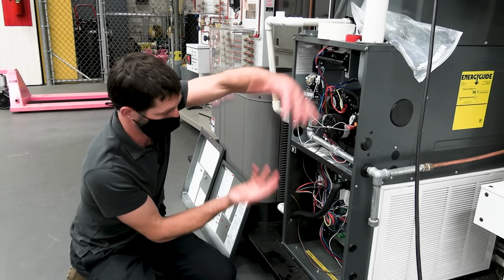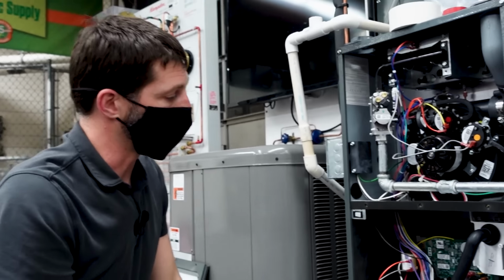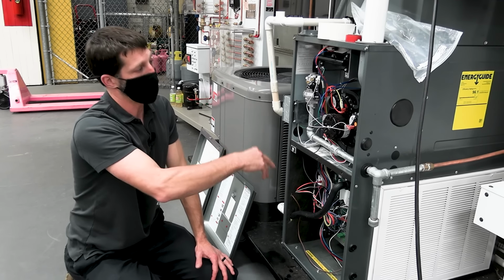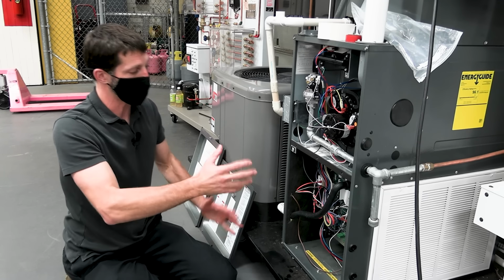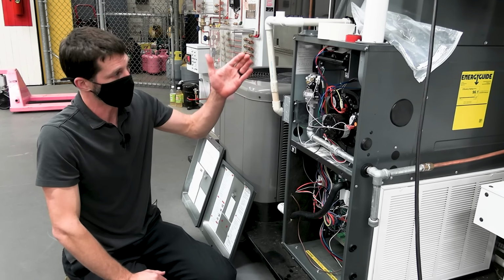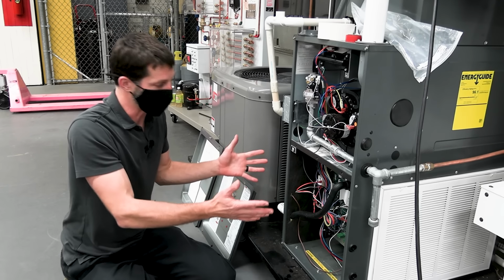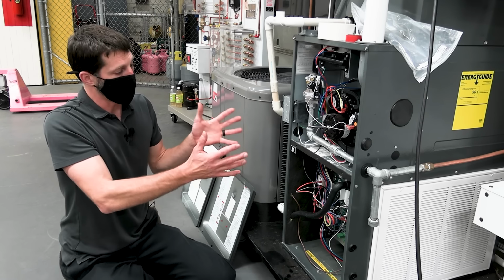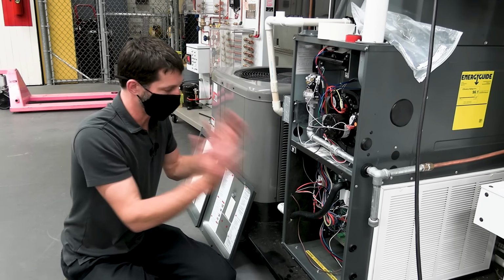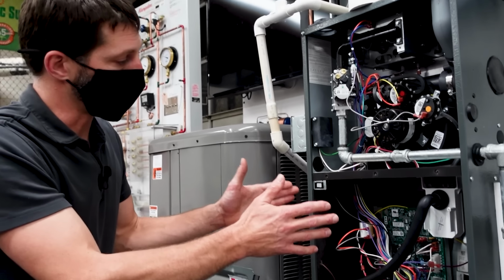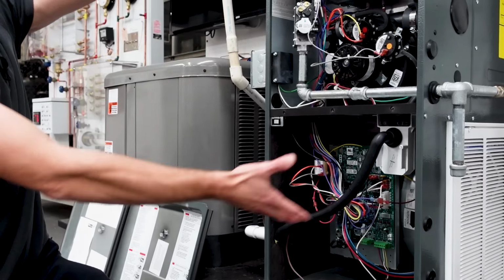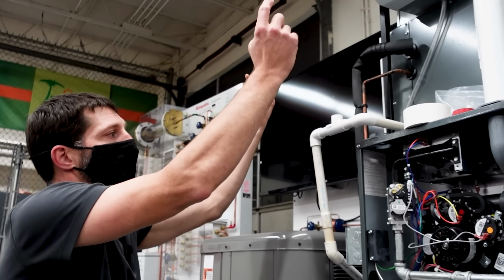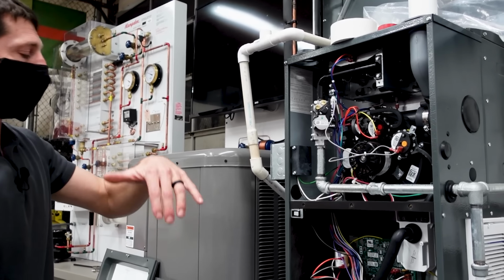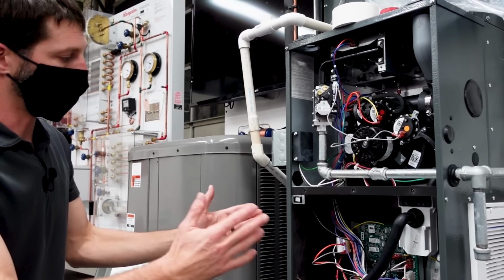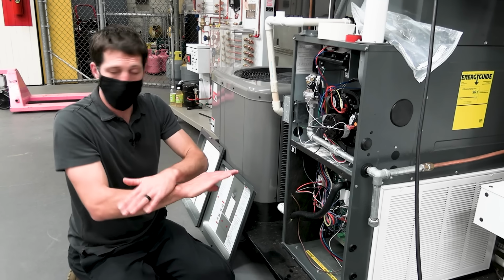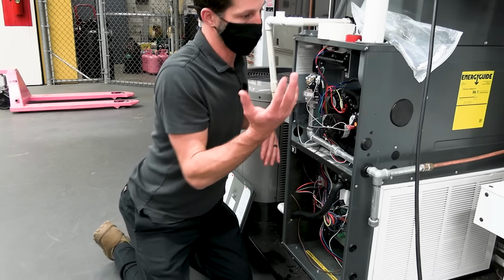They would be doing their job if this was a downflow furnace, because when the gas valve shuts off and the blower motor is still running, it needs to get rid of the heat that was developed by the combustion. And so you're going to have a blower off delay of maybe 90 or 120 seconds, and if for whatever reason it can't get rid of the heat and then it shuts off, those thermal limit switches are up top on the furnace and heat rises, right? So they would trip. And so if you're not supplying the correct amount of airflow or something like that, those would trip. So those are there. They should all be normally in the closed position at your standard indoor air temperatures.